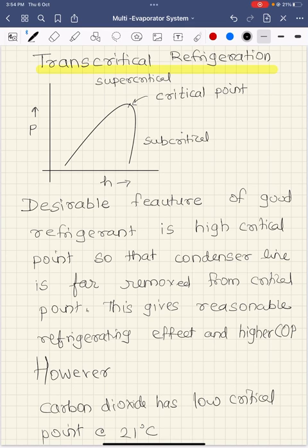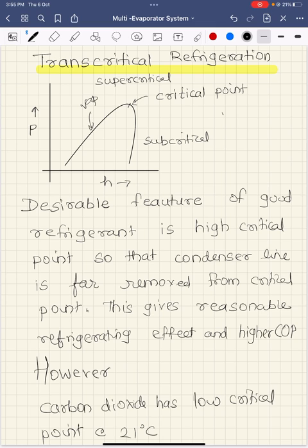Dear friends, this video will explain the concept of the transcritical refrigeration cycle. To understand what a transcritical refrigeration cycle is, we need to look at the pressure-enthalpy diagram. We are familiar with the pressure-enthalpy diagram. This is the vapor dome, and below the vapor dome the region is called the subcritical region. The top of the vapor dome is referred to as the critical point, and below the critical point we have the region where the refrigerant boils.